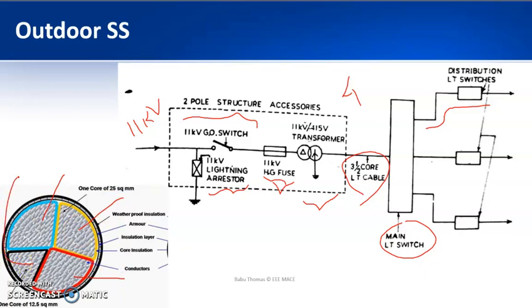In that you can see that this core, the second one and the third one are 25 square mm, but the fourth one is a 12.5 square mm cable. That 12.5 square mm is utilized for the neutral conductor, and the others are used for the R, Y and B phases. In a balanced system the neutral current is supposed to be 0, but the neutral capacity is such that half of the phase conductor size is taken for the neutral conductor.